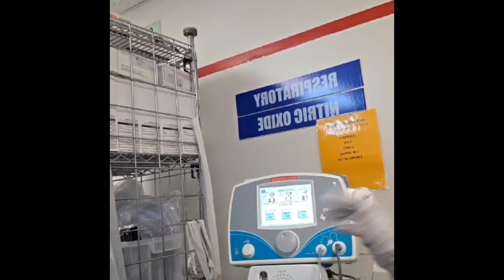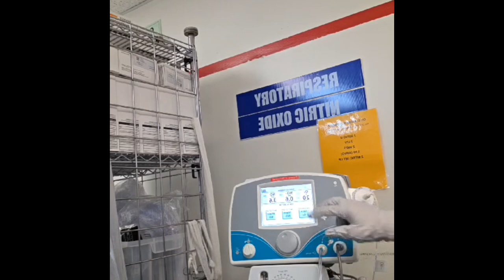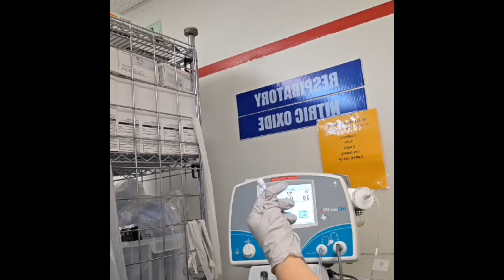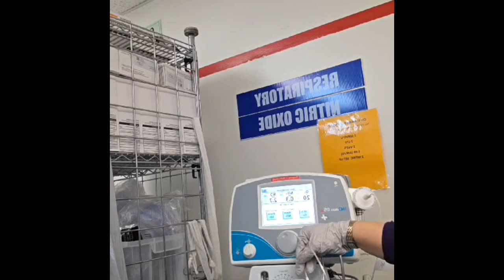Sample line was removed, and now it says all done. You see, now it's due in a month from now. So we did our nitric oxide, our nitric dioxide, and the same thing we can do for oxygen by again grabbing your sample line and just putting it here. Turn up the flow. I'm gonna do it now. As a matter of fact, let me do it now. I hope we have enough in our tank.